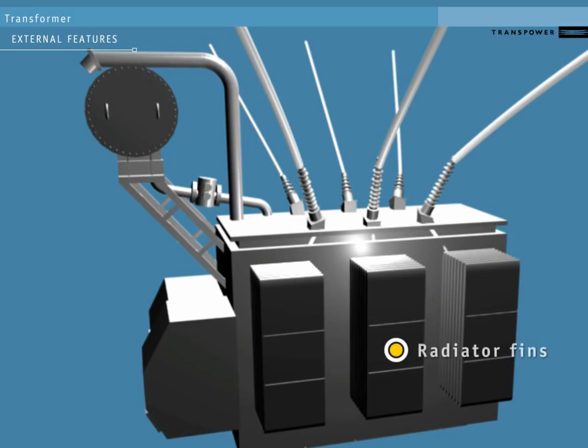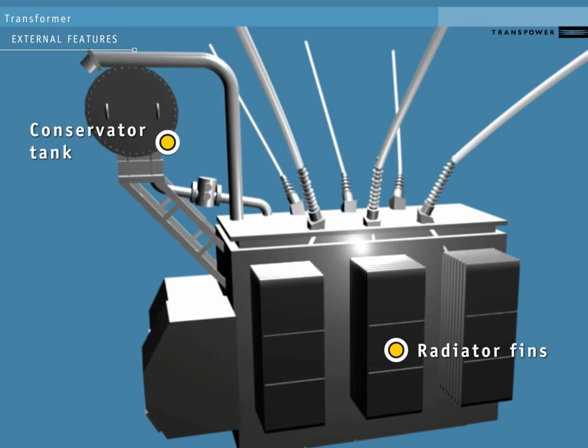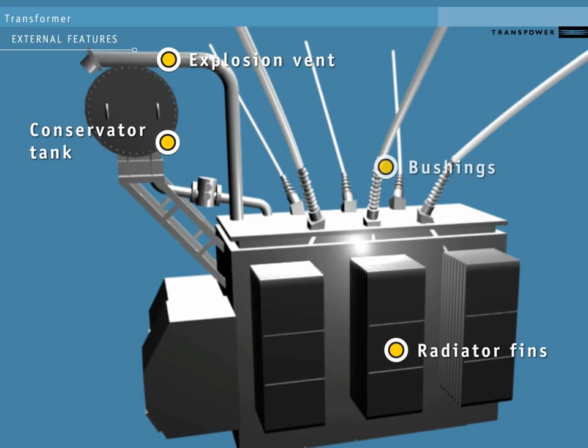The radiator fins help cool the oil in the case. The conservator tank allows for the oil to expand and contract as it heats and cools. The explosion vent protects the transformer in the event of a major fault. The bushings insulate the conductors where they enter the case.